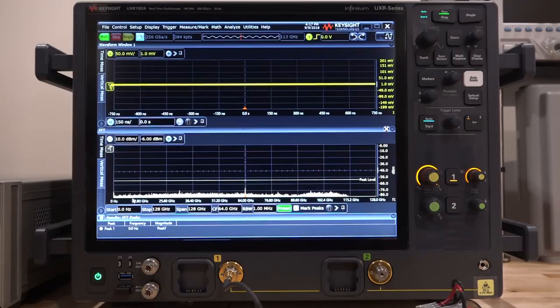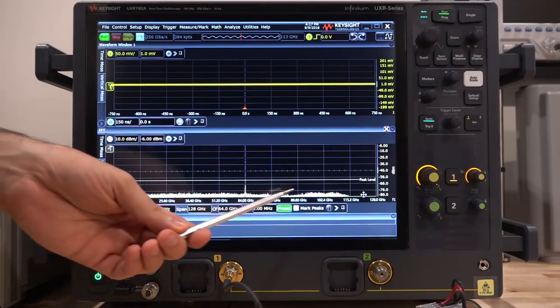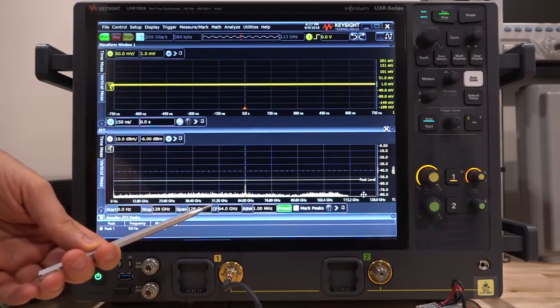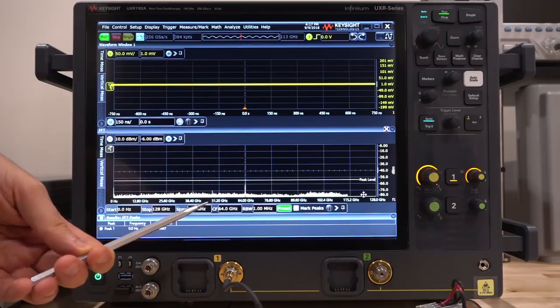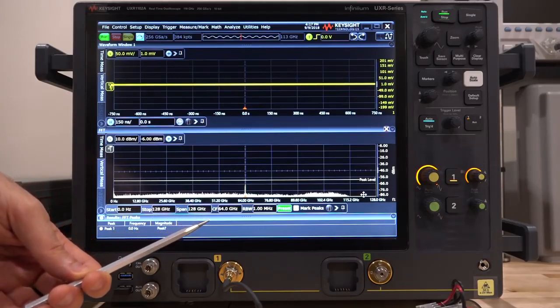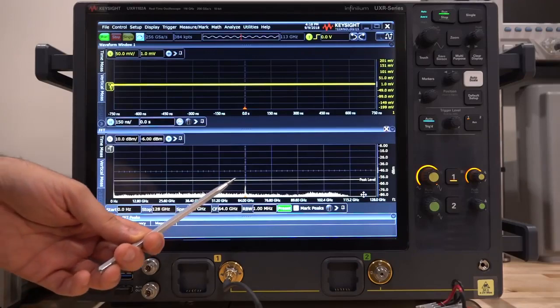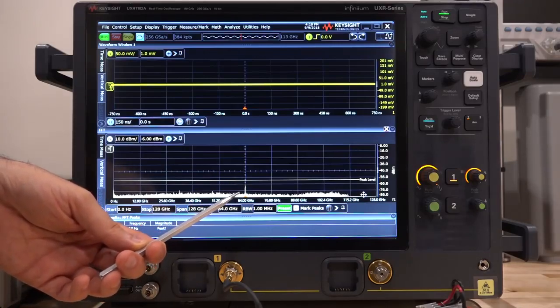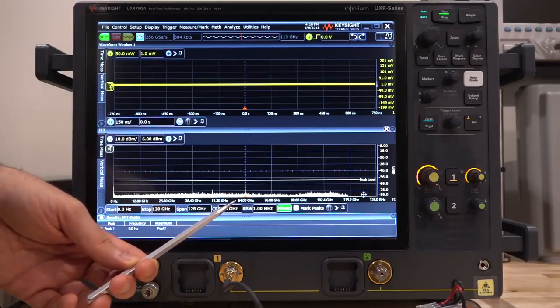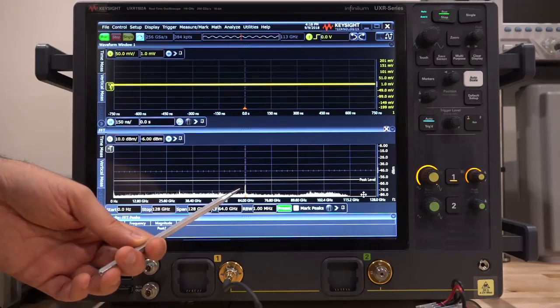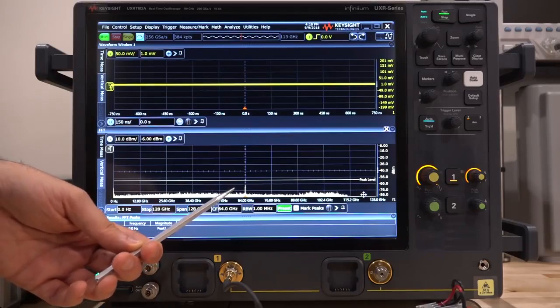And check the noise floor here. The displayed average noise floor for this setting is around minus 80 dBm. This is extraordinary for such a broadband front end for an oscilloscope, and there's nothing connected to the input right now. And take a look, there are almost no tones at the output of this ADC, meaning every single harmonic of every single clock that's generated is so well filtered and so well accounted for. Here there is only a little bit of a signal at 64 gigahertz in the middle of the spectrum, and that's from the front-end sampler. Very difficult to get rid of that signal, but even that is sitting at around minus 76 or 75 dBm on average. And perhaps in the future version, the final version, it might be even better than this.